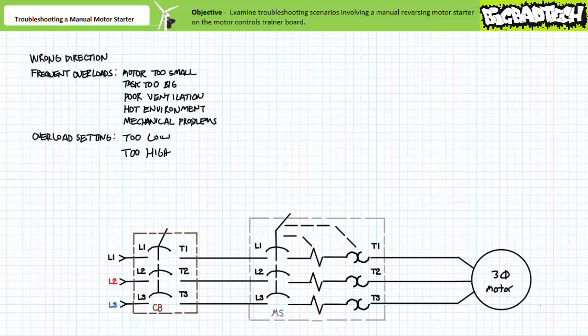In regards to a motor that truly is being overloaded due to some excess task, do not for a moment think that increasing the overload setting above the value as recommended by the process or governing code is an acceptable solution to this problem. The higher overload setting will simply allow more current for a longer time period and runs the risk of eventually damaging the motor and the very real possibility of burning the whole place down.